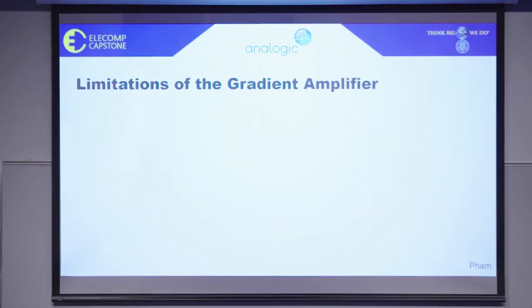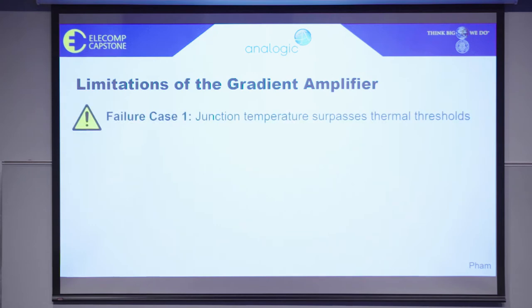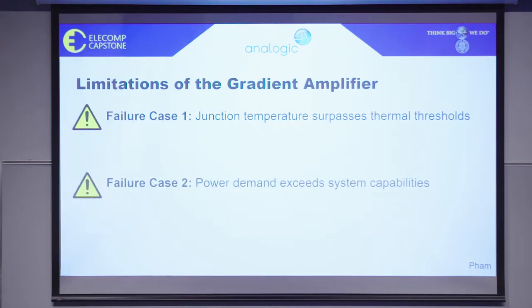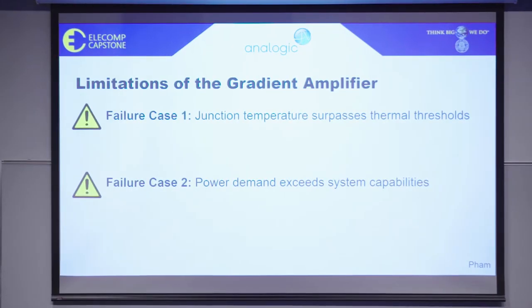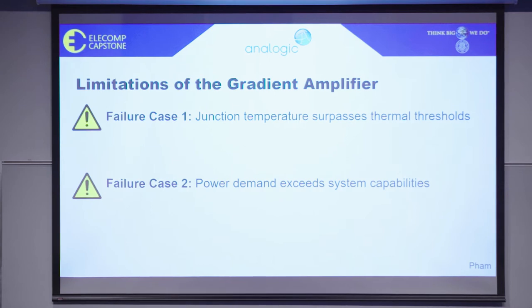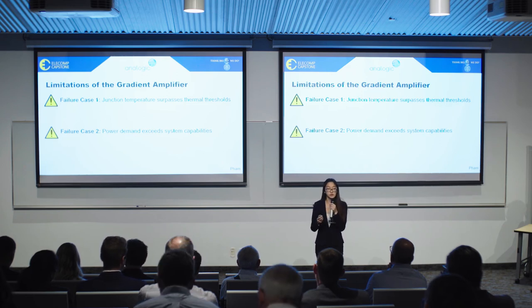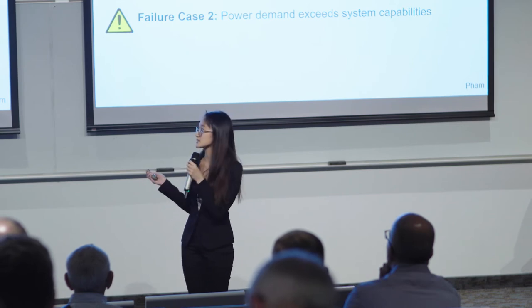There are two limitations of the gradient amplifier we are concerned with. The first is when junction temperatures exceed thermal thresholds, which can cause the controller to trigger a fault and go into automatic system shutdown. The second is when power demands exceed what the capacitor bank can supply, resulting in output waveform distortion and skewed MRI results. This is undesirable as it can lead to reduced system reliability, safety concerns, and increased costs.